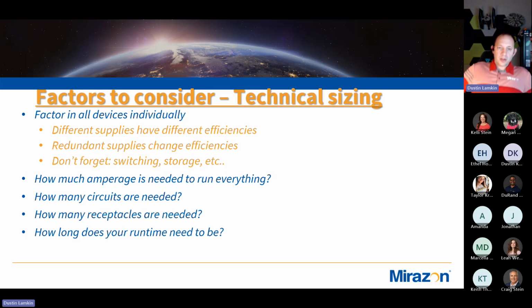So we just need to know what we're getting into. Now, talking about the different devices - let's say you have multiple power supplies. If one of those dies, that's a whole different draw for the single remaining power supply. That changes from a little bit of power on each PDU to all the power on one PDU. So we need to think about that with our PDU sizing. We don't want to just split the load everywhere and think we're good, because if half of it goes off, you're going to blow the other side, and then it's all bad real fast.